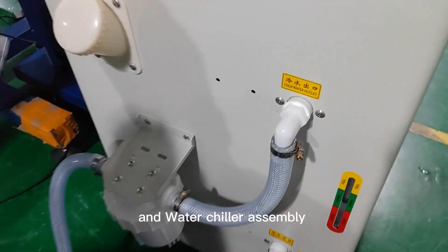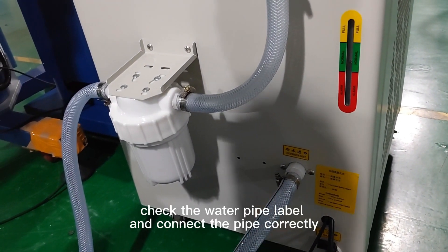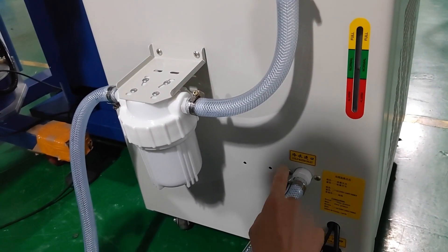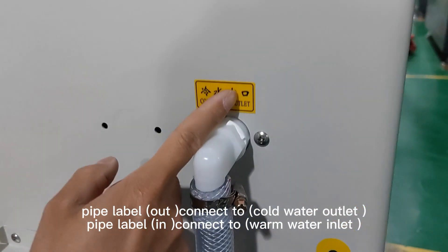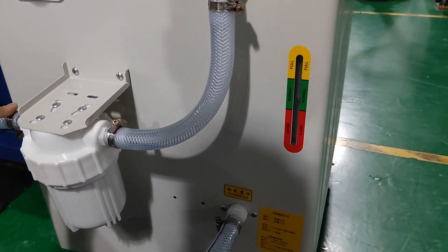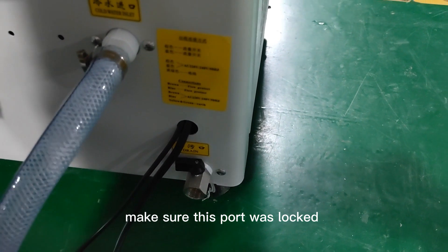For the water chiller assembly, the water pipes have labels showing output or input. Check the water pipe labels and connect the pipes correctly. The pipe labeled 'out' connects to the cold water outlet; the pipe labeled 'in' connects to the warm water inlet. Connect the pipe and tighten the screw clamp. The chiller system has a drain nut — make sure this port is locked.